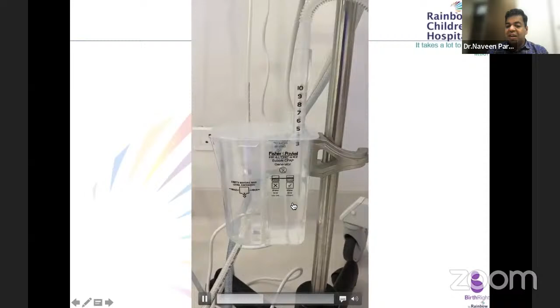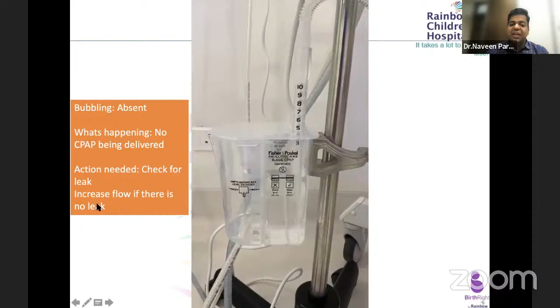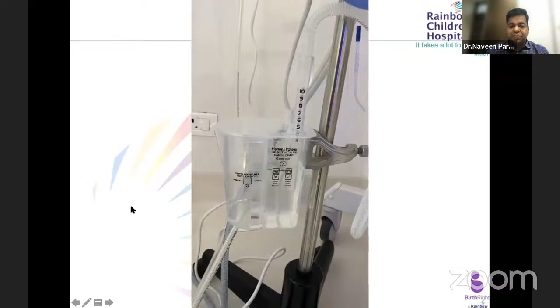Let's look now. Now there is no bubbling happening. You can see the water column moving with inspiration and expiration. So maybe there is a leak at some place. What's happening? No CPAP is being delivered. Action needed: check for the leak, increase flow if there is no leak. Okay, now this is inadequate bubbling at the same flow. What's happening? CPAP being delivered is lesser than set CPAP. Action needed is to check for leak, increase flow if there is no leak.